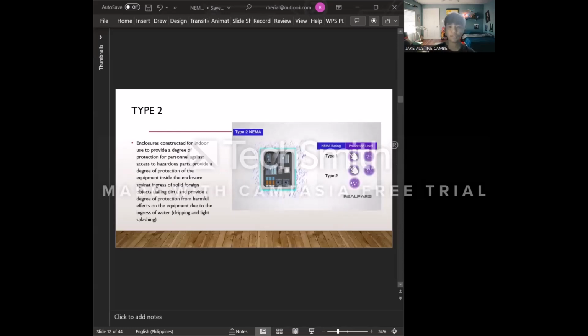Enclosures constructed for indoor use to provide a degree of protection for personnel against access to hazardous parts. Next is to provide a degree of protection of equipment inside the enclosure against ingress of solid foreign objects, for example, falling dirt, and provide a degree of protection from harmful effects on the equipment due to the ingress of water. So, for example, dripping and light splashing.